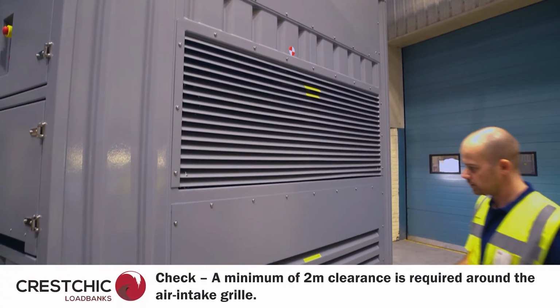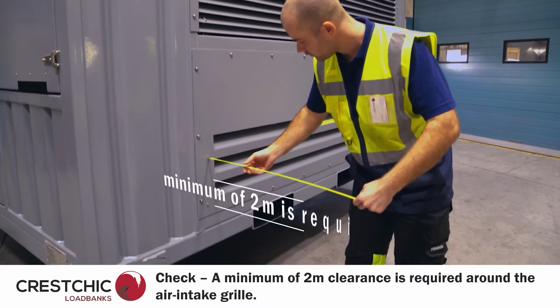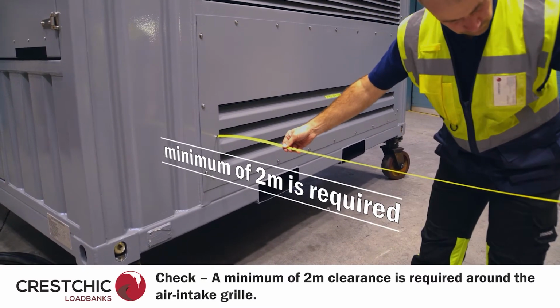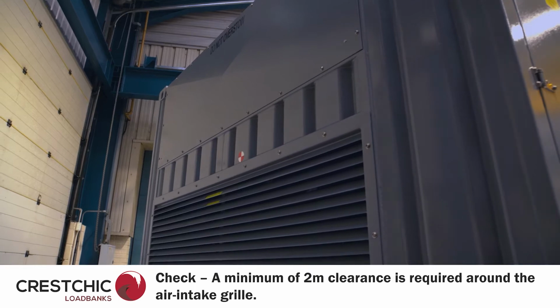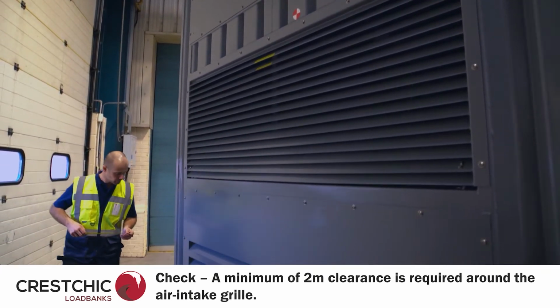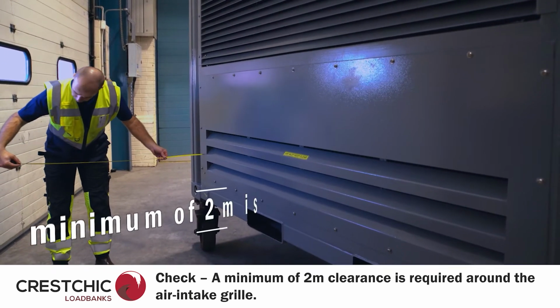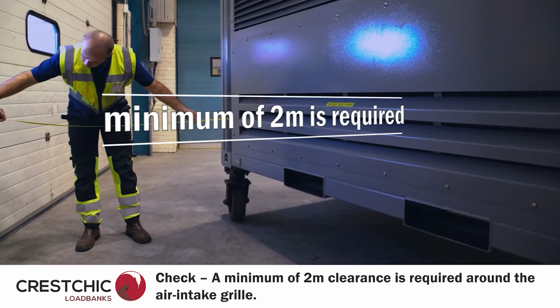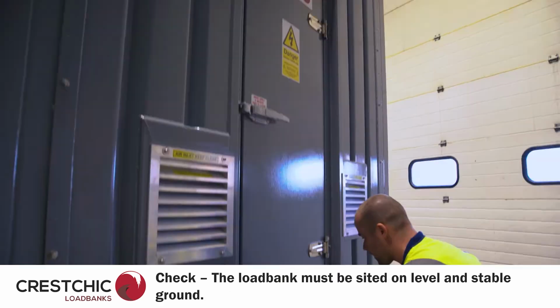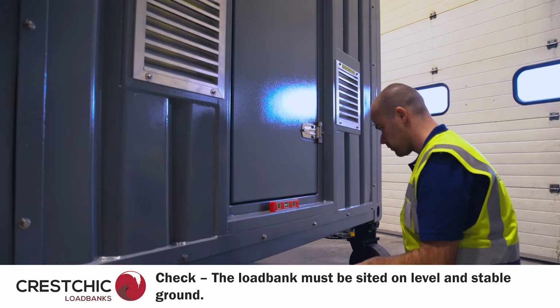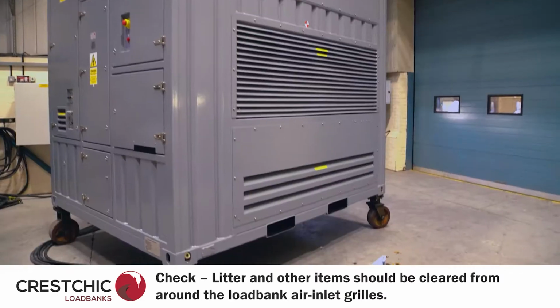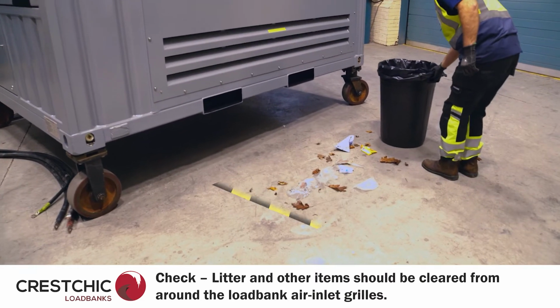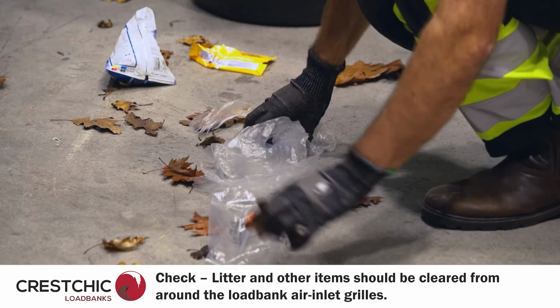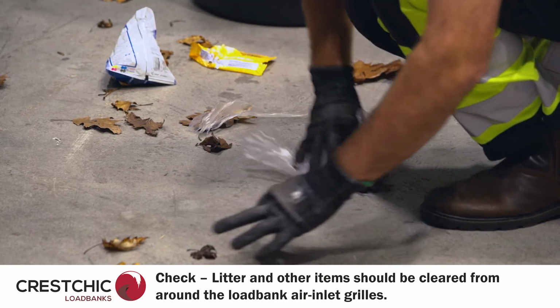Your new load bank will require plenty of space around it, especially where air is drawn in through the air inlet grills. A minimum of 2 meters is required here. Adequate space all around the load bank should be given for future servicing and maintenance. The load bank should be sited on a level and stable surface. We don't want foreign items getting sucked into the load bank. Therefore, check around the load bank for any litter, leaves, etc. and remove these.